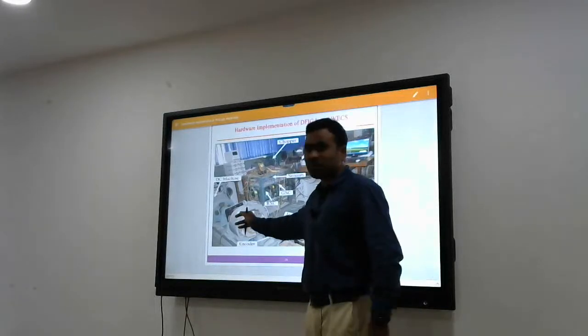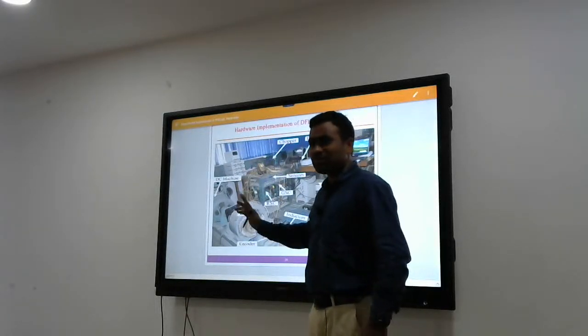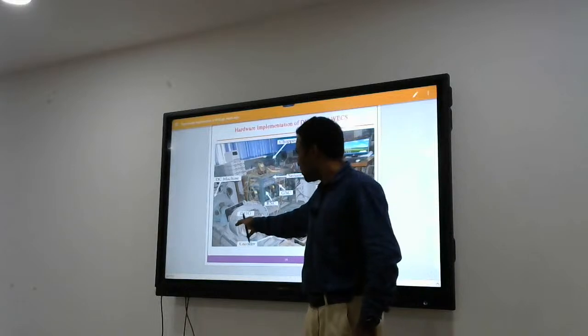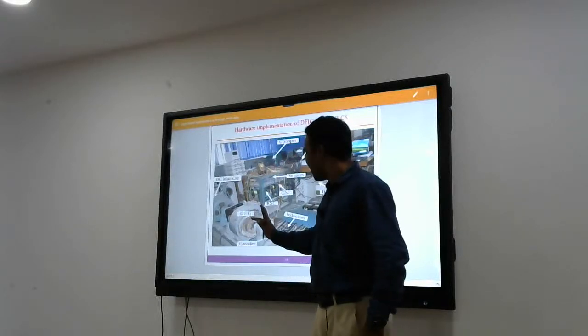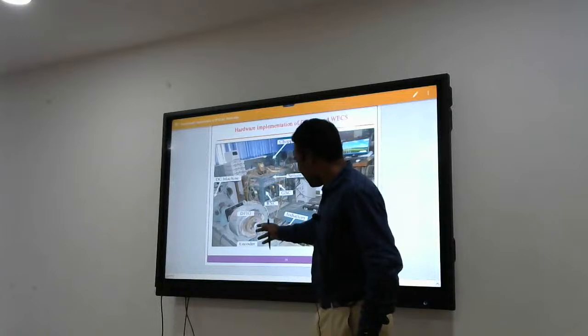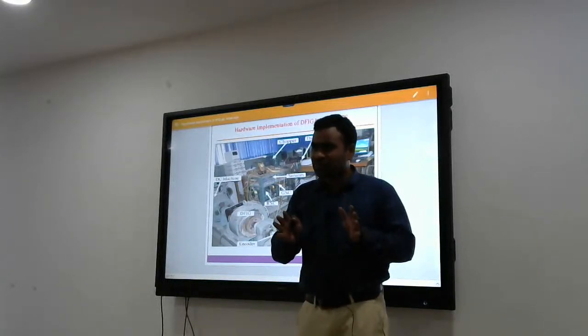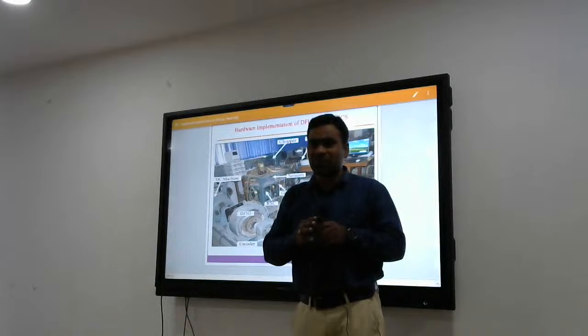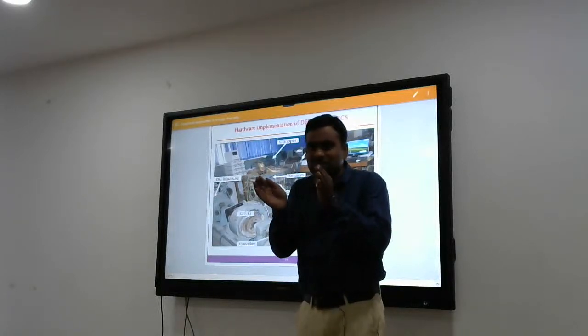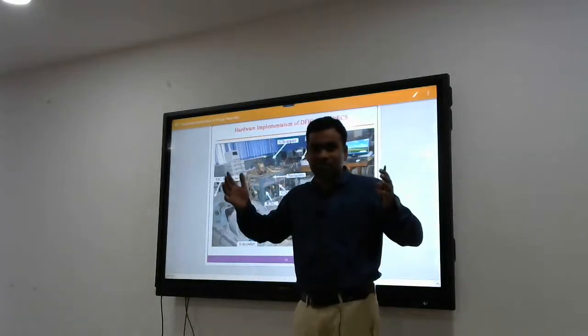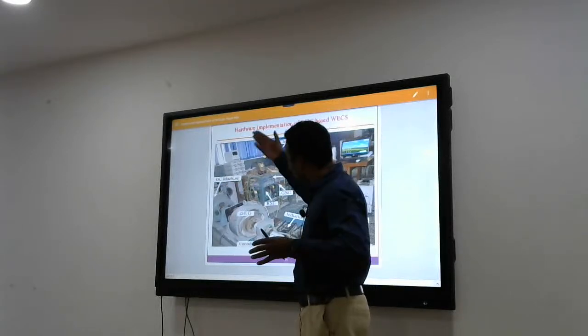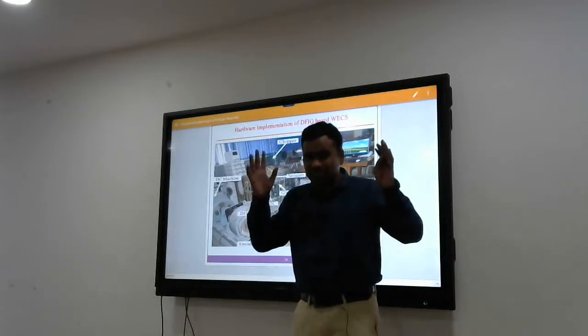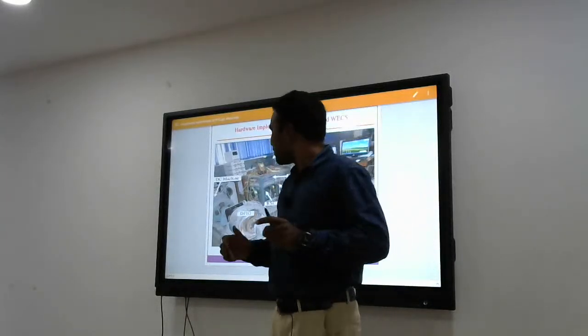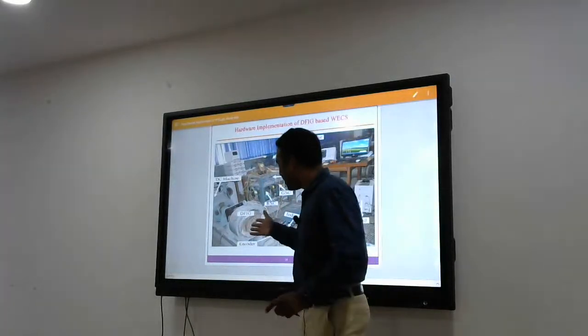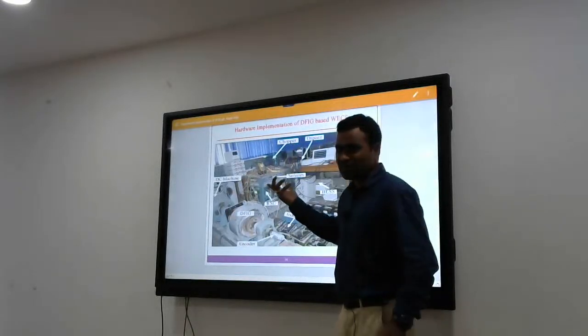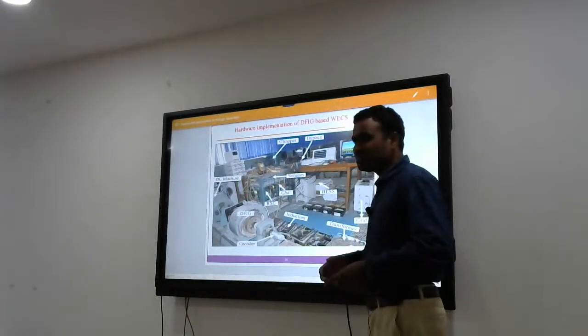At that time they brought this machine from London, UK. Still it's working very well, very robust. These are only 3.7 kilowatt machines. Suppose if we see in your lab, maybe a 3.7 kilowatt machine is this small. Now this is an overrated machine. For 3.7 kilowatt, even if you generate 5 kilowatt, there will not be any problem. At that time it was overrated. You will have good ventilation, good air, so there is no chance of burning and all these things.